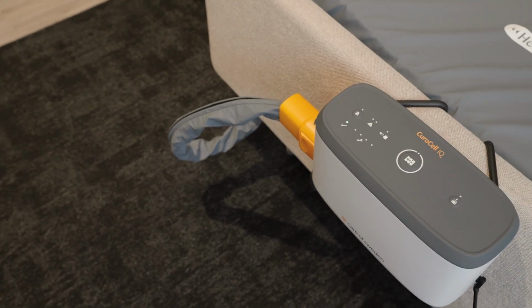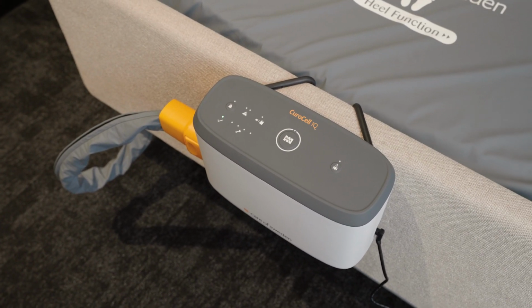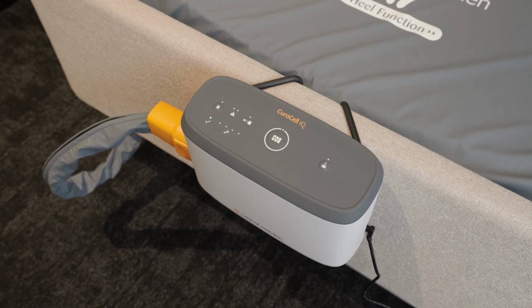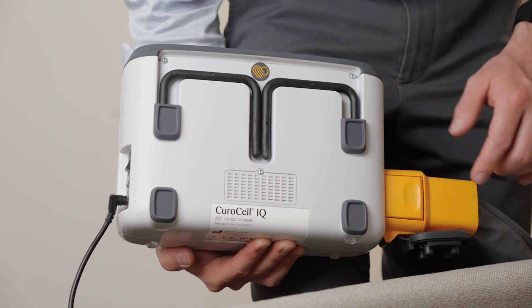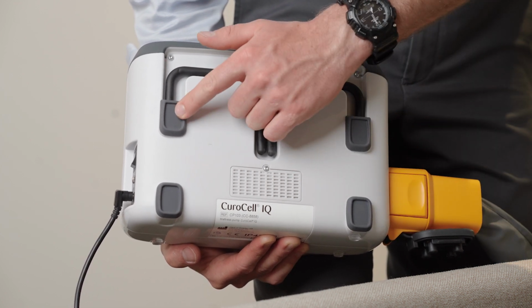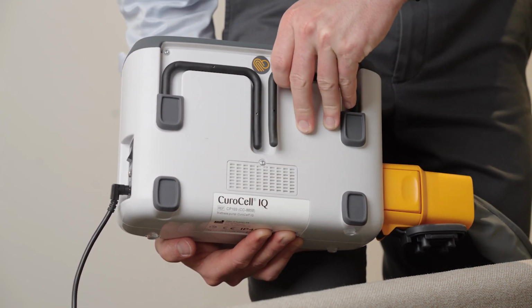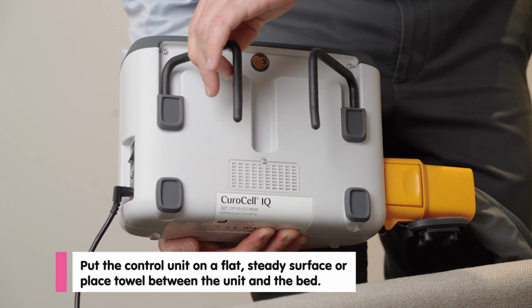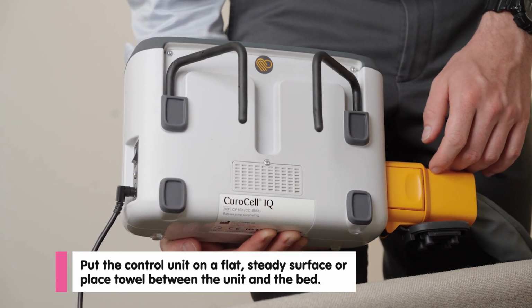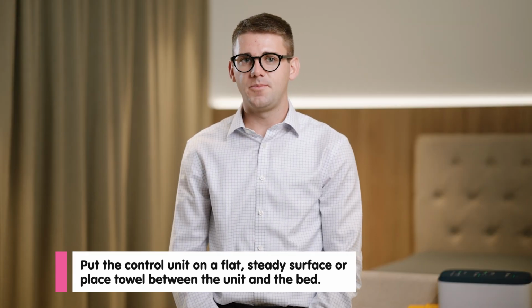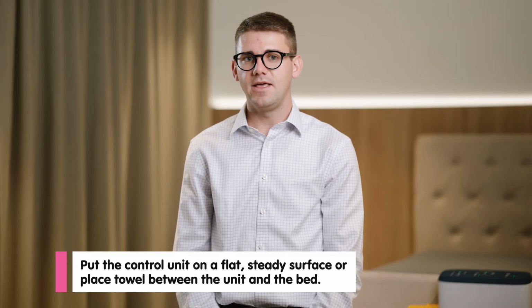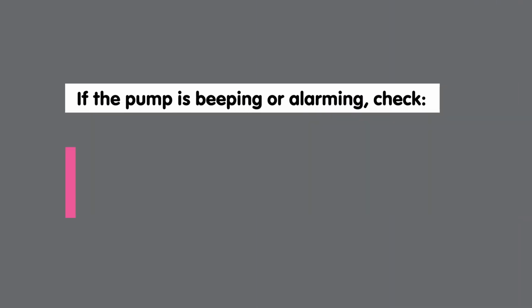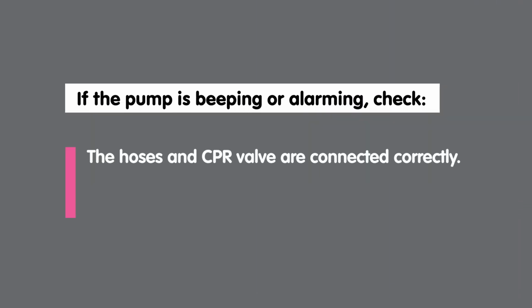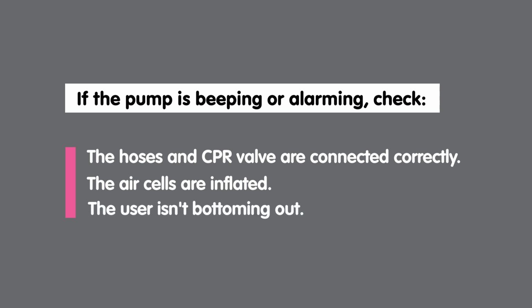If the control unit makes a noise or vibrations can be felt, first check how the control unit is hanging on the bed. Then check, are the rubber stoppers positioned correctly? Are the hangers positioned firmly on the footboard? The problem may be resolved by putting the control unit on a flat, steady surface or by placing a towel between the control unit and the bed. If the pump is beeping or alarming, check the hoses and CPR valve are connected correctly. Check the air cells are inflated and the user isn't bottoming out.